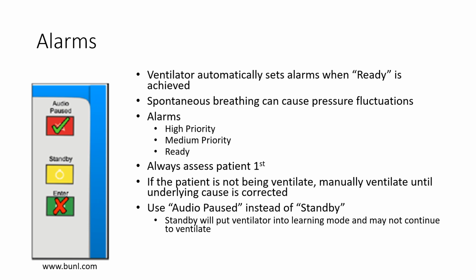A red alarm is high priority and the patient should be immediately assessed for ventilation status. If there is any suspicion that the patient is not being ventilated, they should be immediately disconnected from the ventilator and manually ventilated. When there is an active alarm, avoid pressing Standby as it will put the ventilator back into a learning mode.